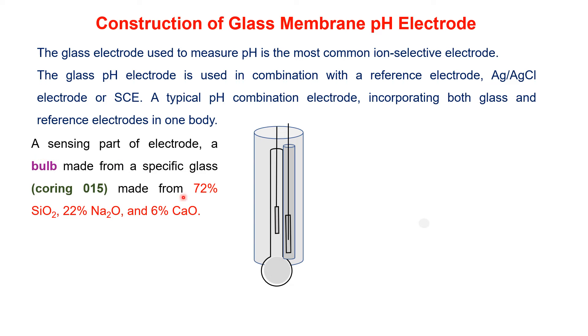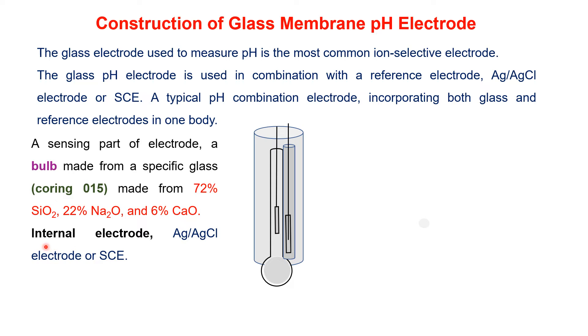The most important part of the glass membrane electrode is the bulb, which is sensitive to specific ions. It is composed of Corning 015 glass for pH measurement, with composition 72% silica, 22% sodium oxide, and 6% calcium oxide. The second part is the internal electrode, which is a silver-silver chloride electrode or saturated calomel electrode inside the glass electrode.